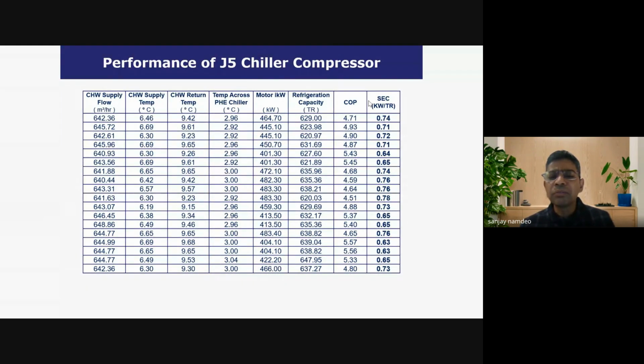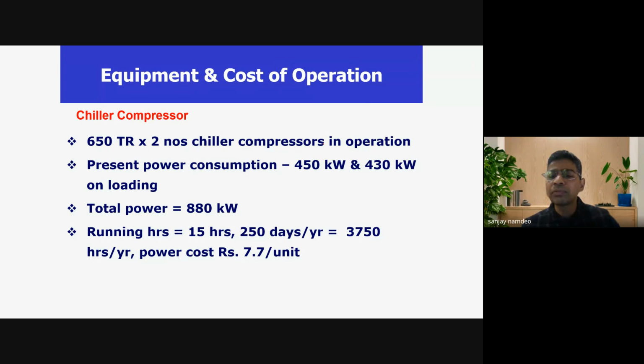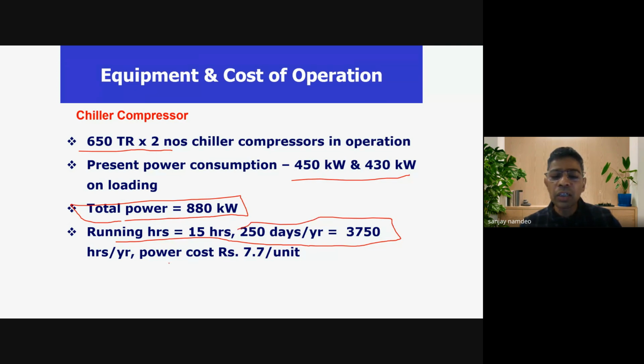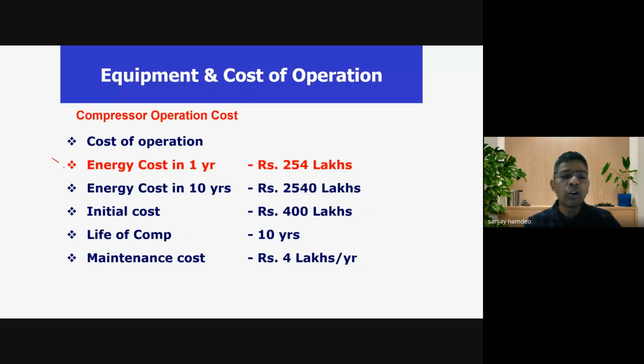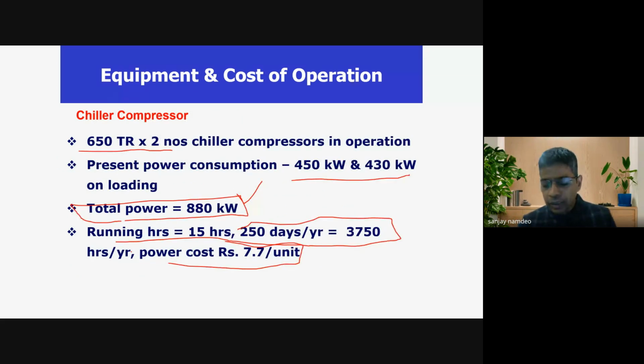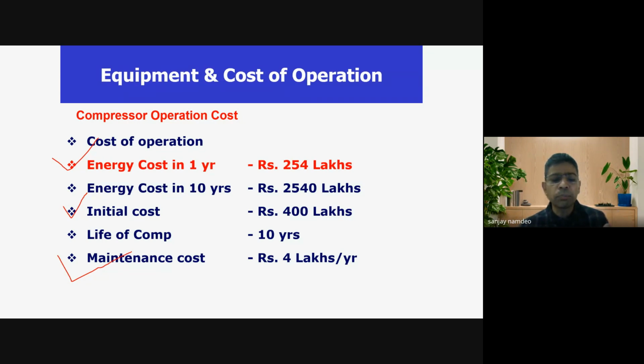So it means any equipment has some energy consumption, right? There is some specific output of this equipment. So there is a total how much power it is consuming, right? Then what we have is the running hours, for how many hours this equipment is running in a year or in a day. And there's a power cost, and based on the power cost, the running hours and the kilowatt, there's a cost of energy which this equipment consumes every year, right? So what are the costs associated with any equipment? The one is the energy cost. The second one is the initial cost when this compressor was bought in the company or when it was purchased. And the third broad cost would be the maintenance cost, right? So in a life cycle cost scenario, the life cycle cost would consist of the energy cost plus the initial cost plus the maintenance cost, right?